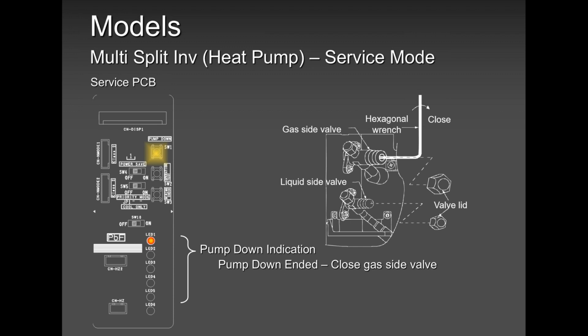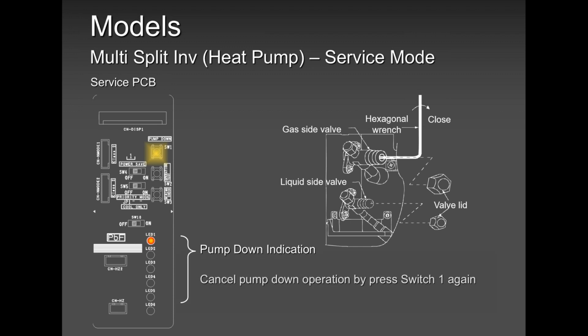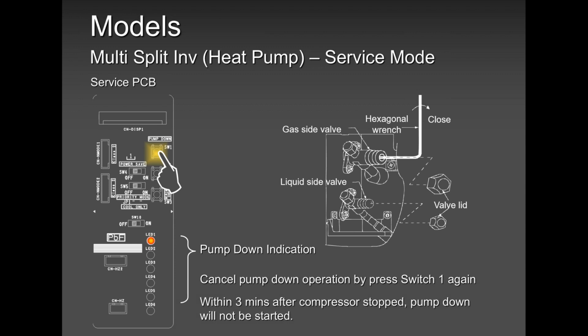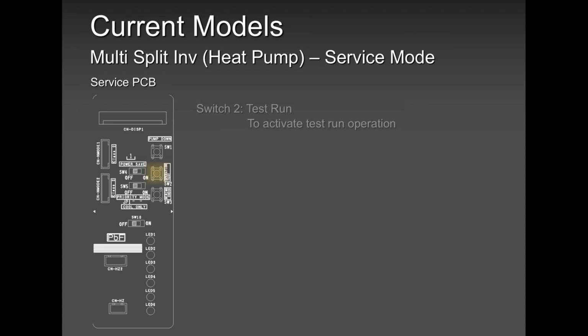Before you're done, make sure you're ready to close the gas valve. Do your stuff, finish, re-vacuum the system, give it a good 50 minute to an hour vacuum, and release the gas again, and you're up and running. For whatever reason, if pump down was not ready but you had pressed it by mistake, you can always cancel the pump down by pressing that same switch again. Now let's talk about test run.